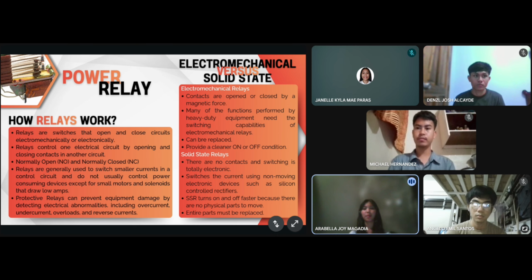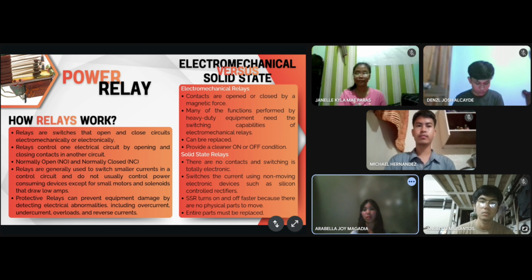So next, let's talk about power relays. As you can see here, we have how relays work and the two main types, the electromechanical and solid-state relays. Basically, a relay is an electrical switch, but what makes it special is that it can open or close a circuit either electromechanically or electronically. So, in simpler terms, relays control one circuit by using a small electrical signal to switch another circuit on or off. This means you can use a small amount of power to control a much larger one. For example, a tiny signal from a control system can turn on a big motor or machine. That's the magic of relays.